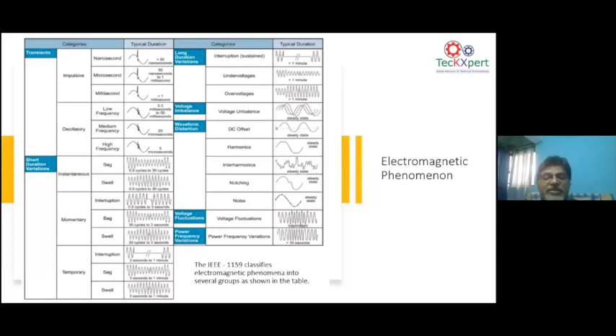Interharmonics are harmonics which are neither odd nor even harmonics. When I say odd harmonics, it is 3, 5, 7, 11. Even harmonics are 2nd, 4th, 6th, 8th. Interharmonics are in between these integer numbers. We call them non-integer numbers.